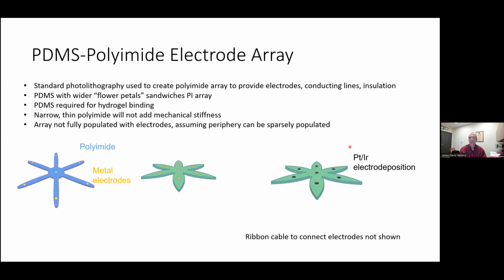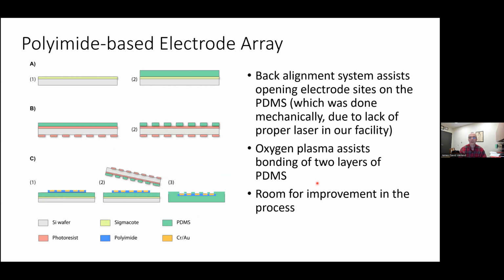Now this has gold electrodes, so what we did is we deposited platinum iridium on this in order to make it robust for electrical stimulation. This is a cross-section of the process where we've got PDMS. We make 2 different layers of PDMS, one which is solid, one with openings. And this was a non-optimal process. We actually had to mechanically go in and scrape out some of the PDMS. So these were fairly large features.